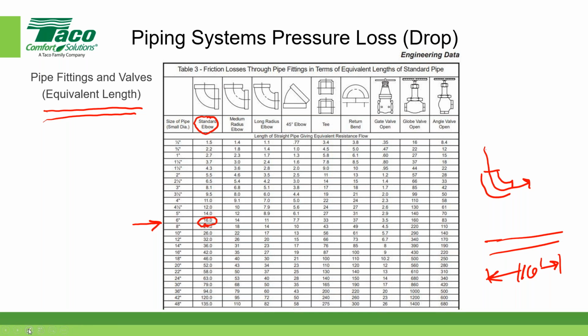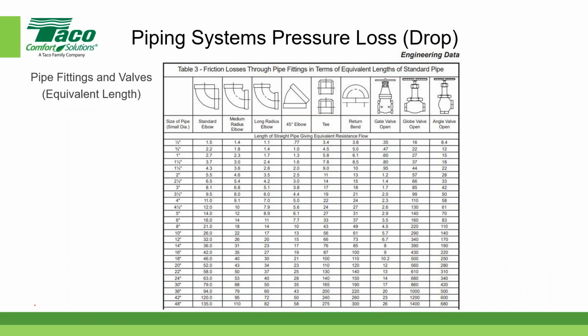Okay. So let's look at a couple of other examples here. The first one is a standard elbow, so check that off. The second one is a medium radius elbow. Look what happens to a long radius elbow. And again, we're going to go back to our 6-inch diameter pipe. The long radius elbow has an equivalent length of 11 feet. So you can see that if I chose to design my system and I used standard elbows in lieu of long radius elbows, I'd have a slightly higher pressure drop. So one of the ways in which we control pressure drop in the system is by selecting fittings that have less pressure drop or a shorter equivalent length. Okay.